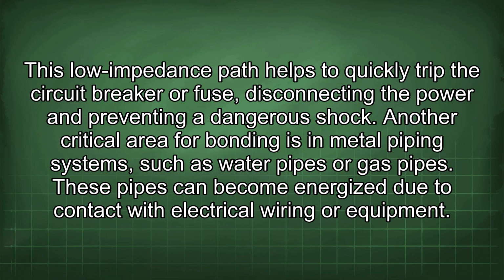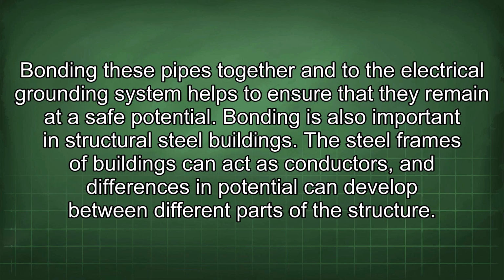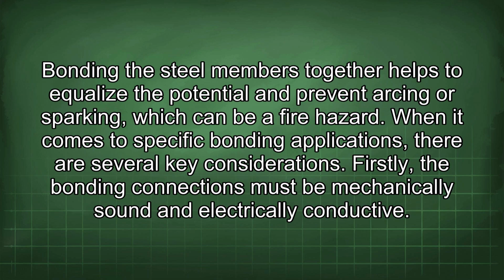Another critical area for bonding is in metal piping systems, such as water pipes or gas pipes. These pipes can become energized due to contact with electrical wiring or equipment. Bonding these pipes together and to the electrical grounding system helps to ensure that they remain at a safe potential. Bonding is also important in structural steel buildings. The steel frames of buildings can act as conductors, and differences in potential can develop between different parts of the structure. Bonding the steel members together helps to equalize the potential and prevent arcing or sparking, which can be a fire hazard.